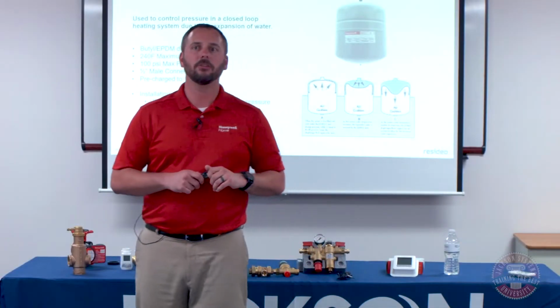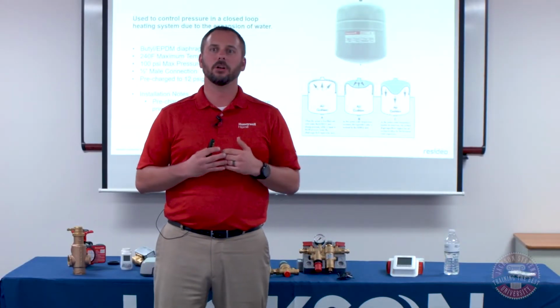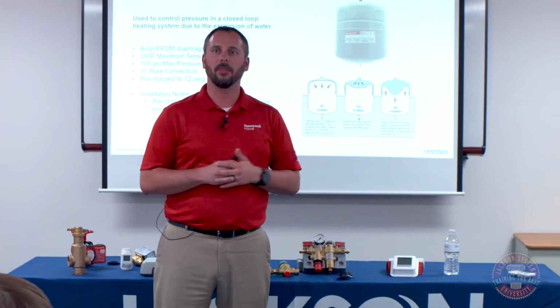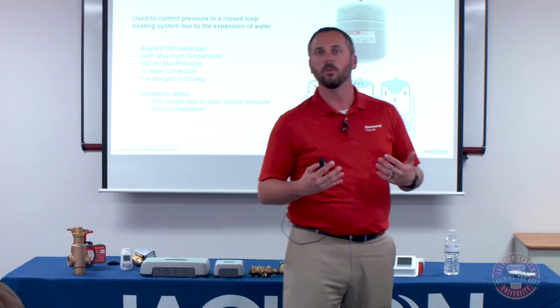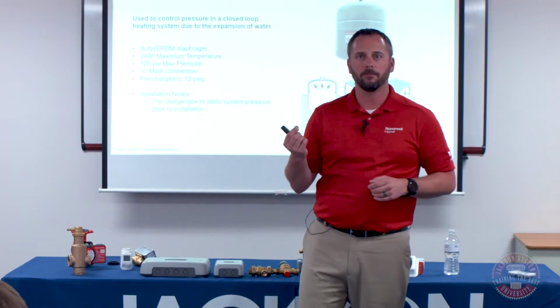Always try to match these to the configuration of your static pressure. So we just talked about that. Let's say in this example that we're coming to 15 psi for the system that we want to run. Before you hook the expansion tank up, there's a little Schrader valve on the bottom of it. You want to pressurize that to 15 psi.